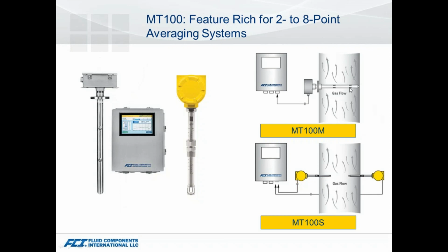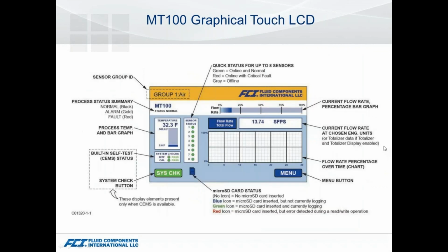So that's kind of the different versions of the MT100. You'll hear the M for the single mass type sensor and the S for the single point sensors. What makes this one of the most fully featured transmitters we offer is a large color touch interface, giving us information, again, graphically on our flow rate, temperature as well, sensor status. Depending upon how many sensors we have in the system, we can see if it's still within the range. And over here in the center, I can actually plot things. I can plot my temperature or my flow rate graphically over time.